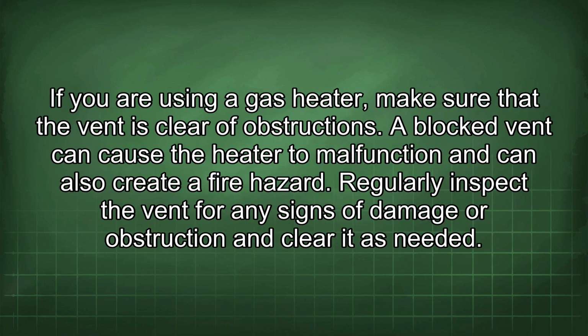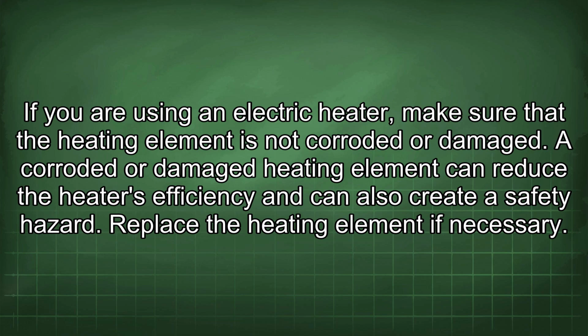pool. If you are using a gas heater, make sure that the vent is clear of obstructions. A blocked vent can cause the heater to malfunction and can also create a fire hazard. Regularly inspect the vent for any signs of damage or obstruction and clear it as needed. If you are using an electric heater, make sure that the heating element is not corroded or damaged. A corroded or damaged heating element can reduce the heater's efficiency and can also create a safety hazard. Replace the heating element if necessary.